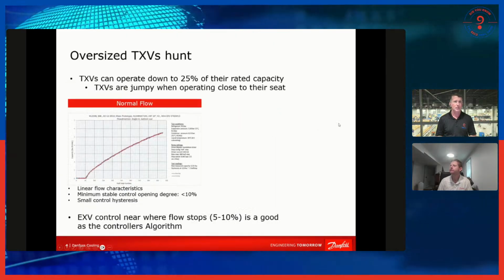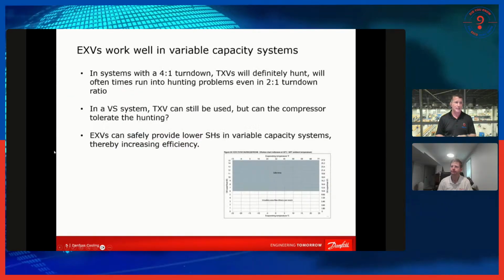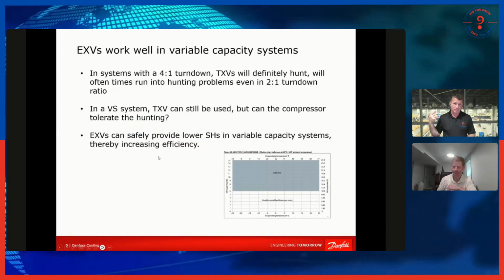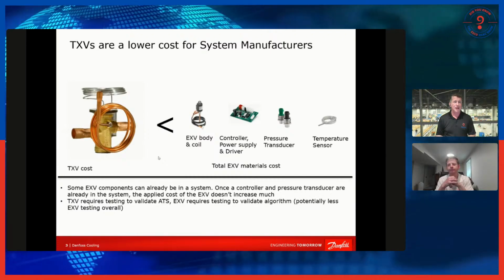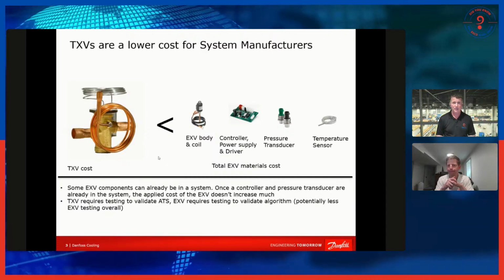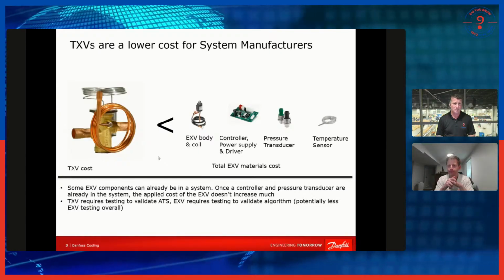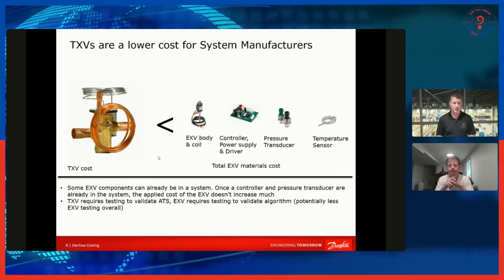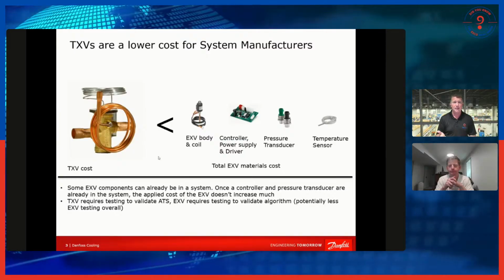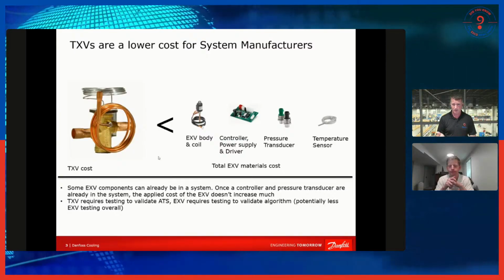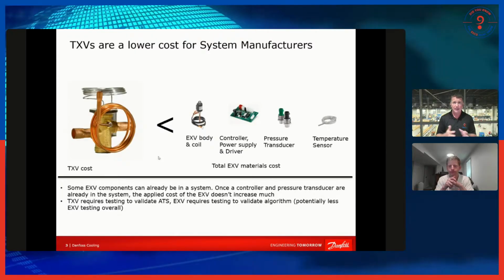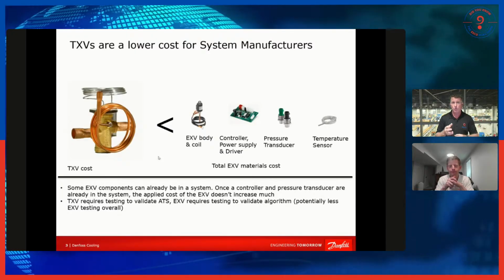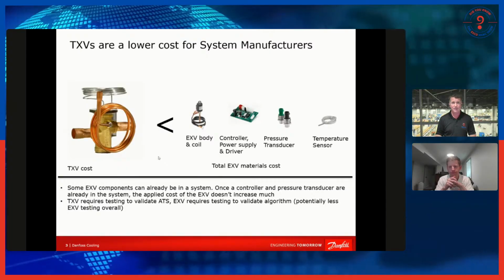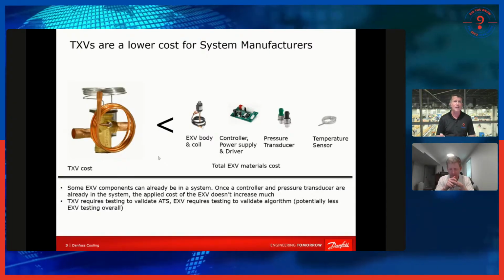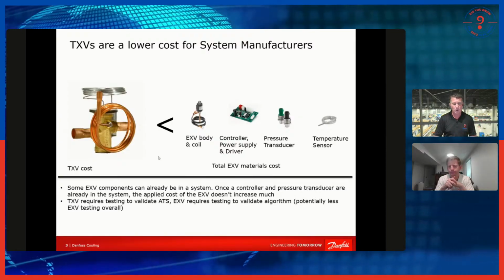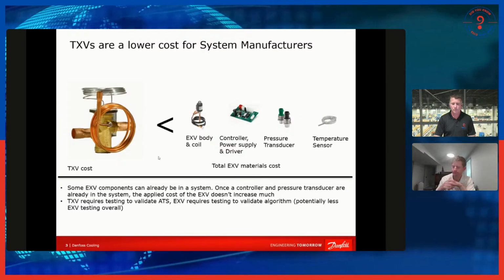Yeah, when we start looking at that progression of equipment, we have many manufacturers of equipment represented at the conference, and they all say the same thing: that the days of single stage and two stage equipment, especially in the residential light commercial split system era, are just about ending, and that the only single stage equipment they're going to be using is going to be their builder grade, and that a majority of their products are starting to move from TXV into EXV components. So it's critical that we understand how they operate as they start moving into the market even further. Definitely, I agree.